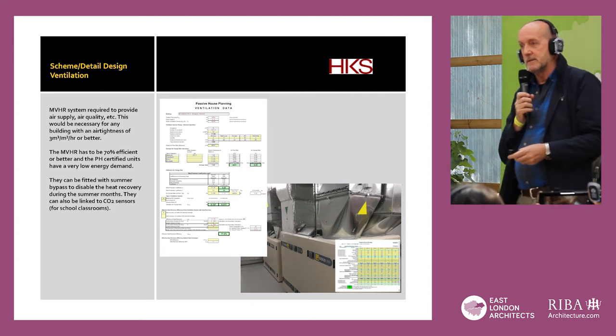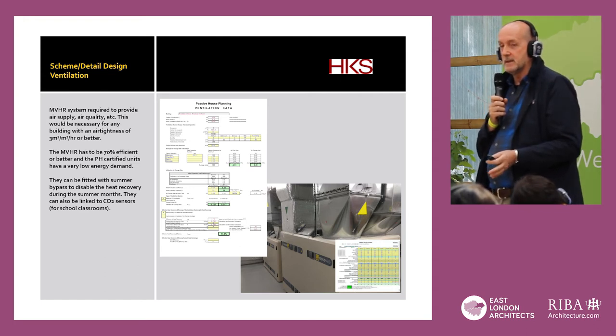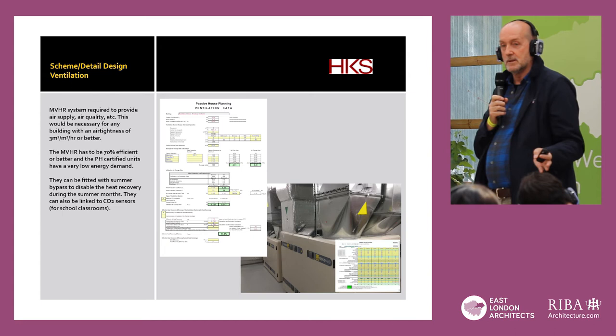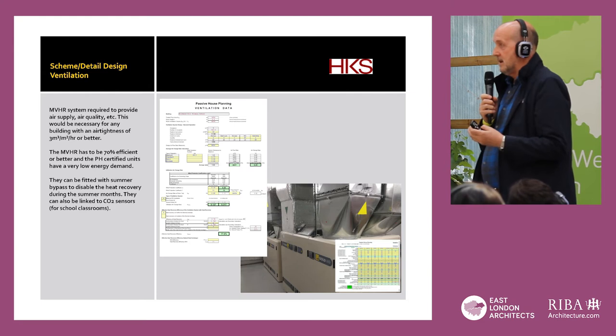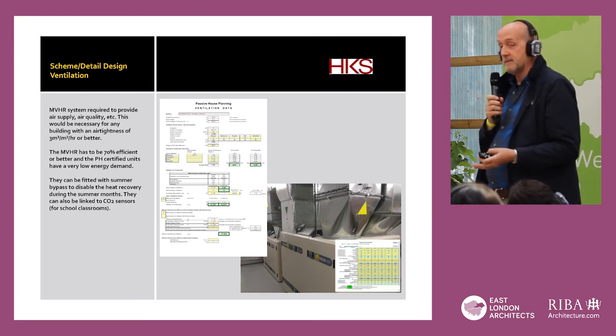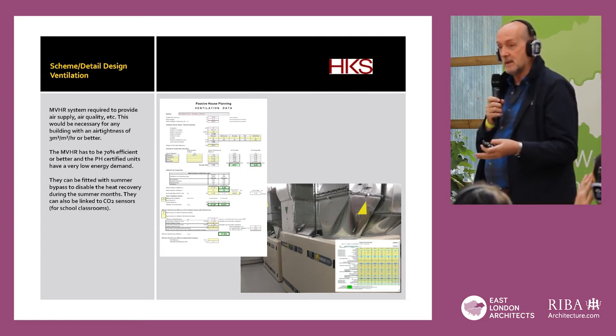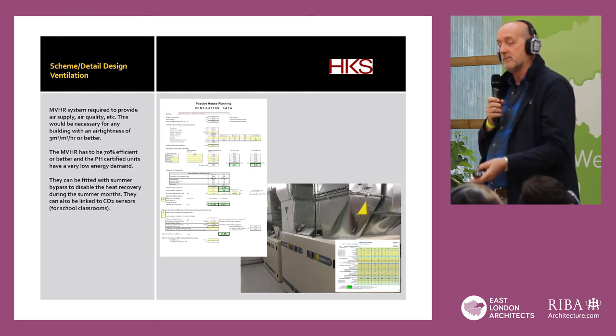Mechanical ventilation with heat recovery — don't believe anybody that says you can build a school purely with natural ventilation. Unless you've got dual-aspect classrooms with windows on both sides and you exclude all still days, you just aren't going to get the ventilation you need. Passive House mechanical ventilation systems must be, at minimum, 70% efficient and they have to be certified — the Passive House Institute must see proof that they can achieve that efficiency. You can get MVHR units that are 80–90% efficient. They run on very low energy, moving air all the time, but recovering the heat.